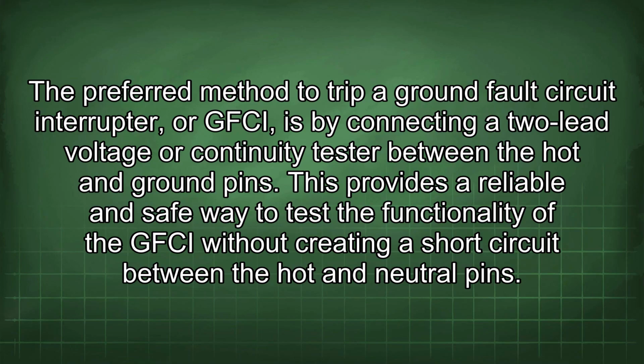The preferred method to trip a ground fault circuit interrupter, or GFCI, is by connecting a 2-lead voltage or continuity tester between the hot and ground pins. This provides a reliable and safe way to test the functionality of the GFCI without creating a short circuit between the hot and neutral pins.